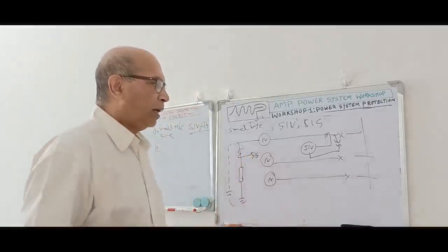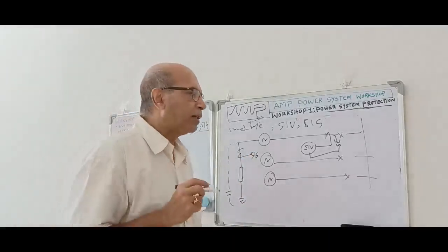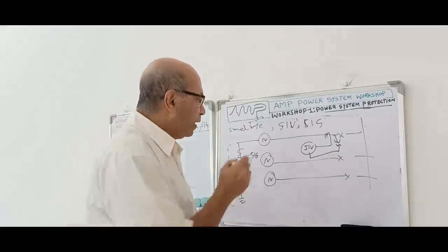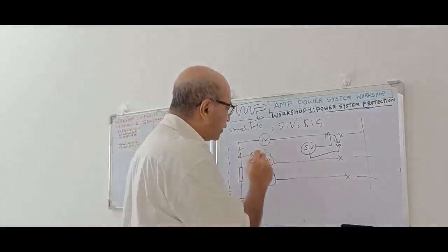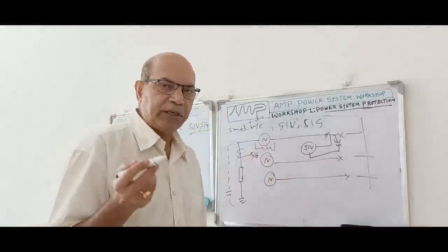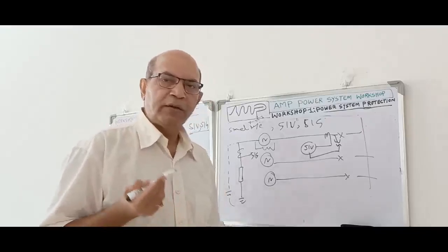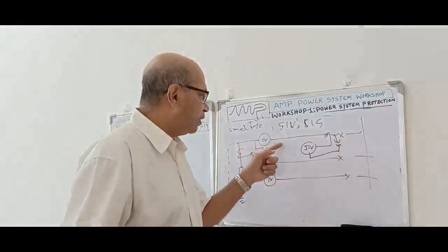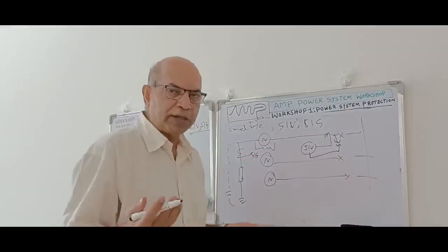Now, in addition to this, what are the other things required when it is running in parallel? The generator is getting rotor supply from the field. If the rotor supply fails, we have seen in case of loss of excitation what will happen. It will take the kVA from the system, the machine will go unstable and become out of synchronism.